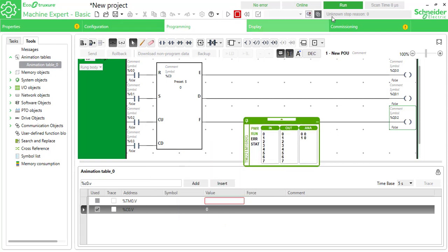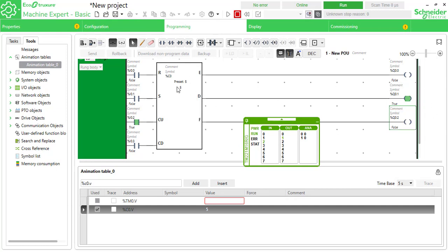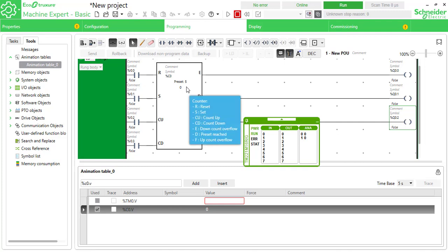In runtime, I0.2 is the up-counting bit. Pressing it, the current counter value increments — one, and by toggling on/off it keeps increasing. When it reaches the preset of five, you get the done bit output. To reset, use I0.0 input — toggling reset brings the current value back to zero.